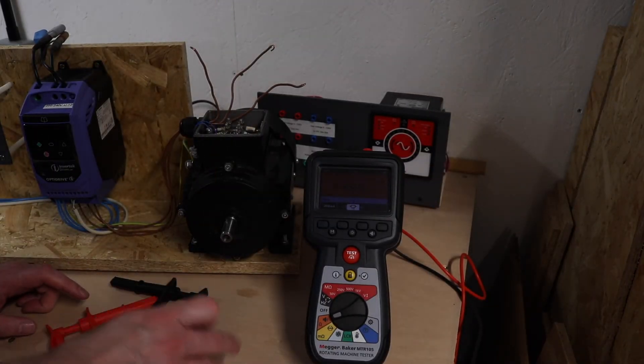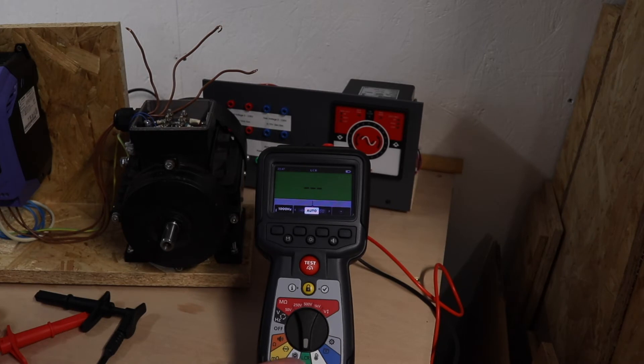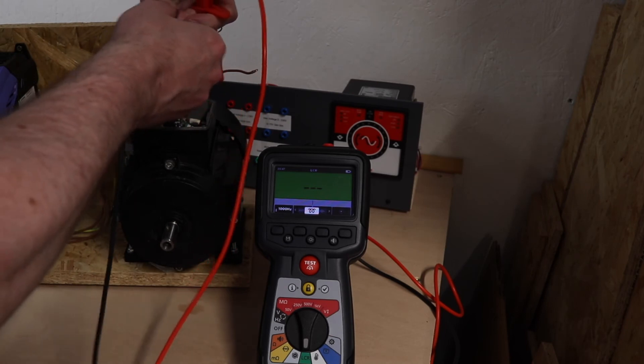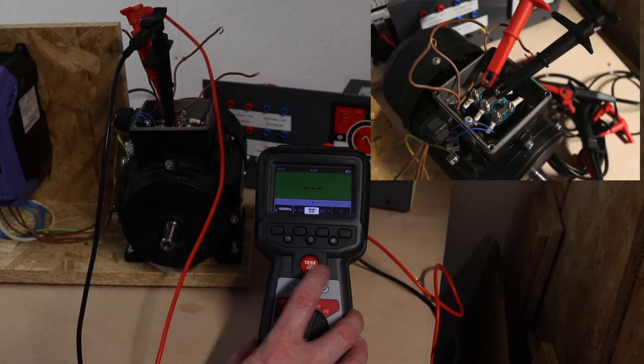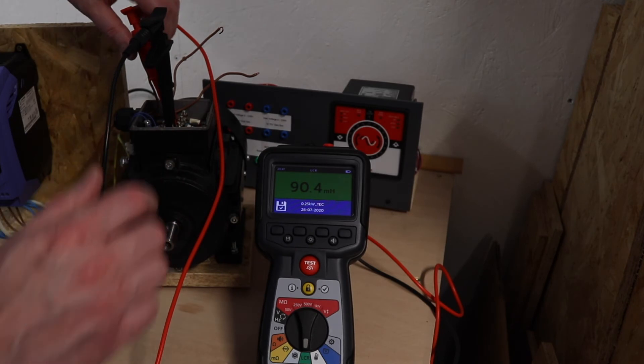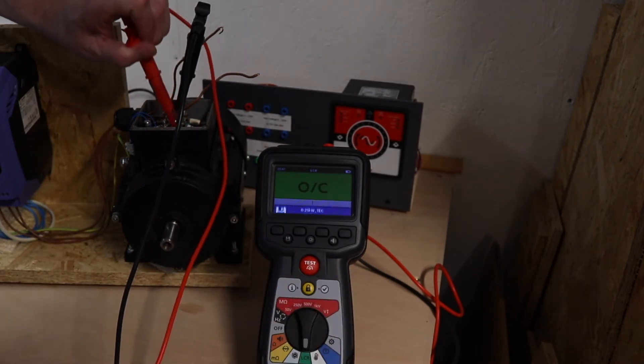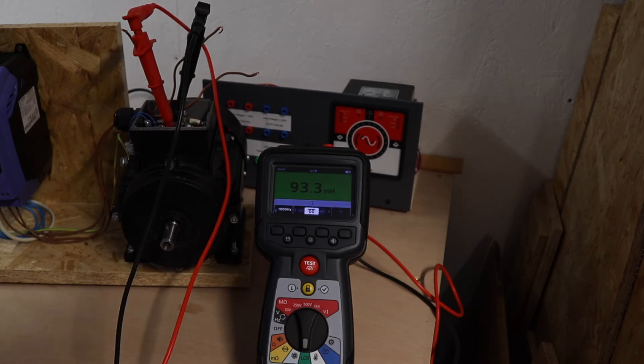The next motor test is Megger's way of detecting an inter-turn winding fault, using the LCR function to measure inductance. I'll switch it to inductance with the same connections and same leads. I hit the test button and I'm looking for a balanced reading across phases. Once you've started the tests off it does them automatically after that. Again, nicely balanced — no problems there.